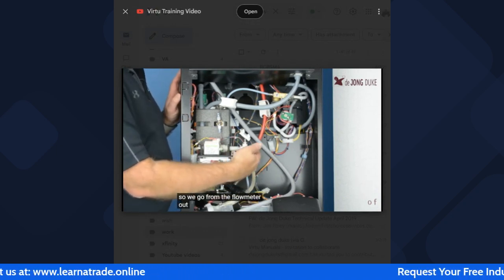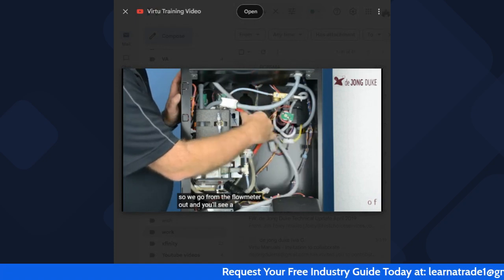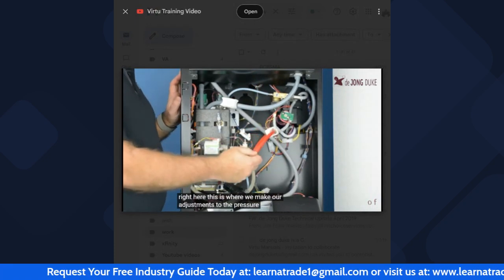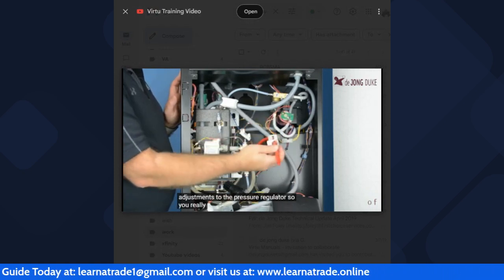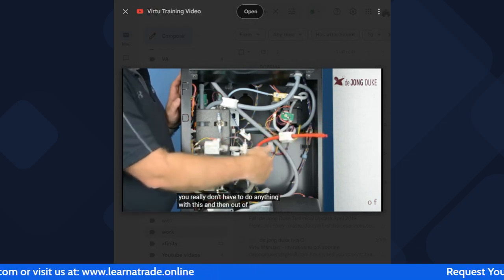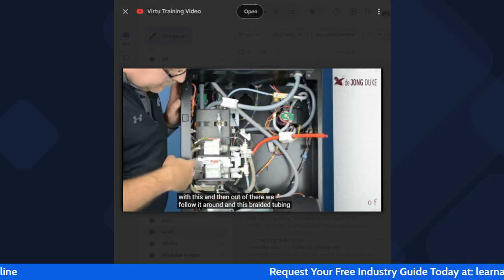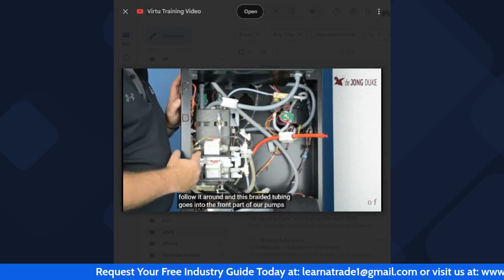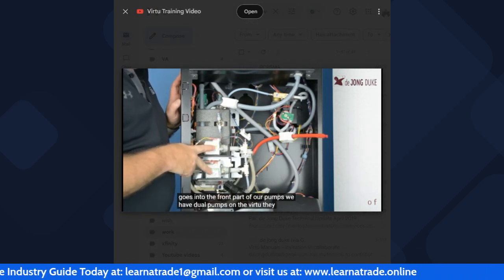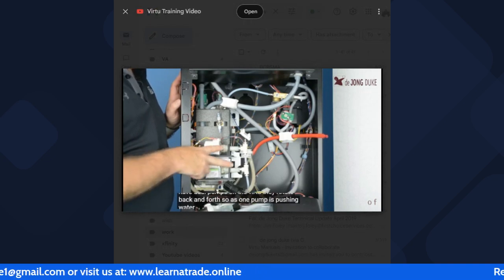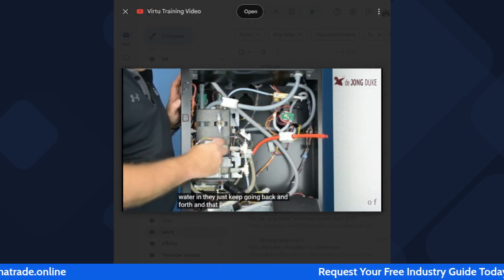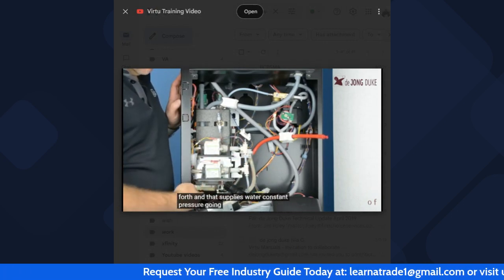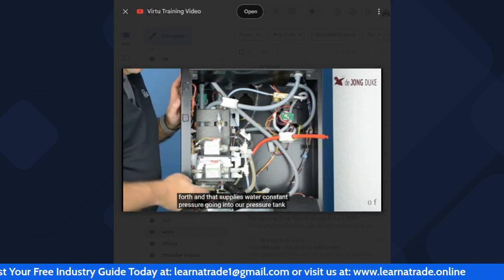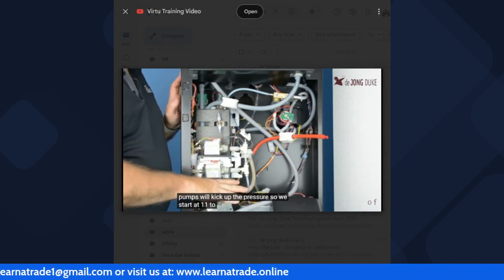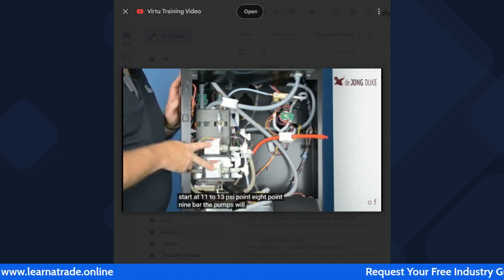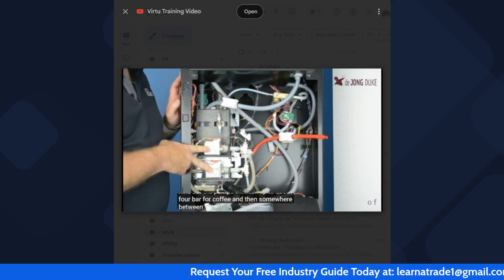So we go from the flow meter out, and you'll see a piece of tubing right here. This is where we make our adjustments to the pressure regulator. So you really don't have to do anything with this. And then out of there, we follow it around, and this braided tubing goes into the front part of our pumps. We have dual pumps on the Virtu. They rotate back and forth. So as one pump is pushing water out, the other one's bringing water in, and they just keep going back and forth. And that supplies water, constant pressure, going into our pressure tank. Pumps will kick up the pressure, so we start at 11 to 13 psi, 0.8, 0.9 bar. The pumps will kick up to about 4 bar for coffee, and then somewhere between 9 and 10 bar for espresso.